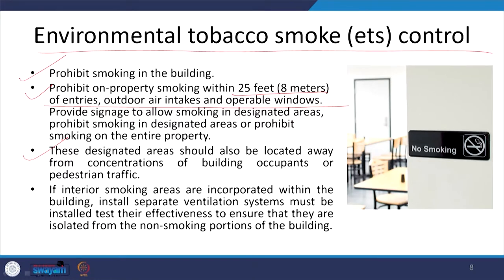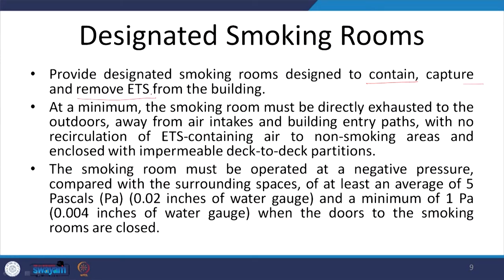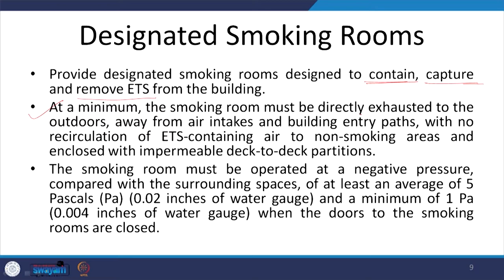If an interior smoking area is provided it must have a separate ventilation system — it cannot share the same air ventilation system as the rest of the building. Designated smoking rooms inside the building must be designed to contain, capture, and remove environmental tobacco smoke from the building, achieved both passively through design and through active systems. At a minimum the smoking room must be directly exhausted to the outdoors, and this exhaust should be away from air intakes and building entry paths so that ETS does not re-enter the building.